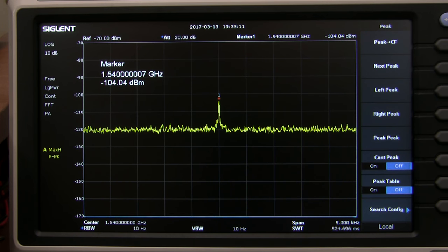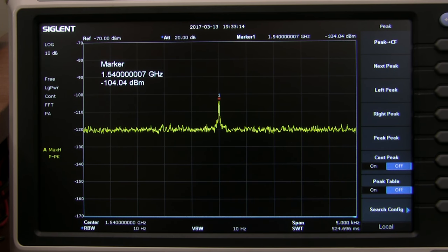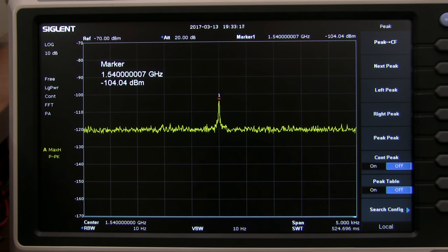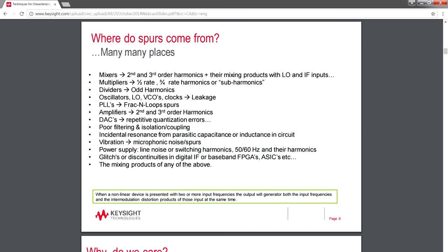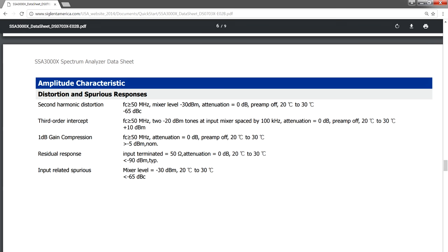Now there's another non-ideality that I want to talk about. Spurious readings, or spurs. There is no such thing as a perfect spectrum analyzer, and what often ends up happening during sweeps is you get measurements of signals that don't actually exist. Check out this webpage on more details for why this can happen. Spurs can pop up in ways that seem almost random, depending on your frequency, span and bandwidth settings. It's extremely time consuming to try all the possible combinations, but I want to document as many as I can in this review, so RF beginners don't get confused by them.